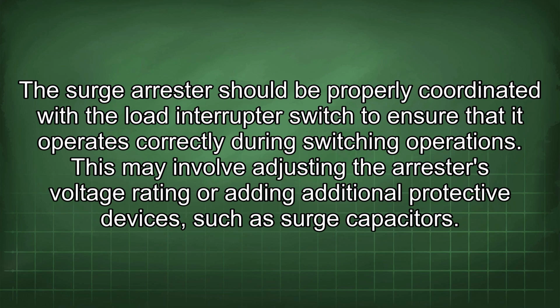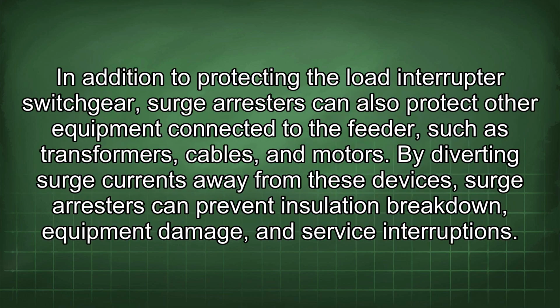The surge arrestor should be properly coordinated with the load interrupter switch to ensure that it operates correctly during switching operations. This may involve adjusting the arrestor's voltage rating or adding additional protective devices, such as surge capacitors. In addition to protecting the load interrupter switchgear, surge arrestors can also protect other equipment connected to the feeder, such as transformers, cables, and motors. By diverting surge currents away from these devices, surge arrestors can prevent insulation breakdown, equipment damage, and service interruptions.